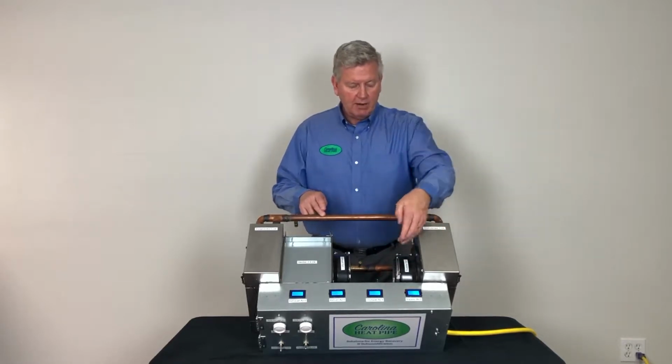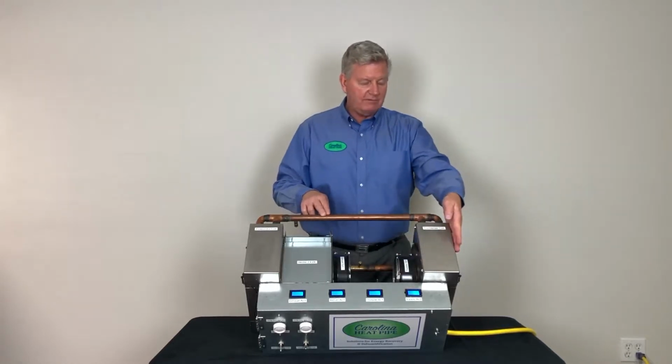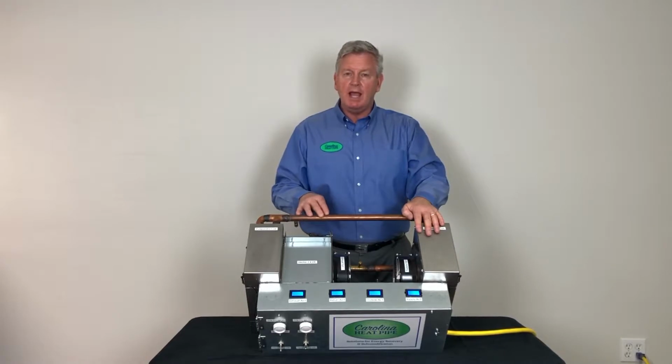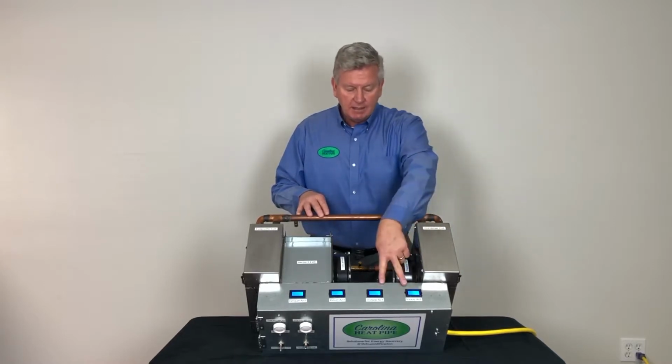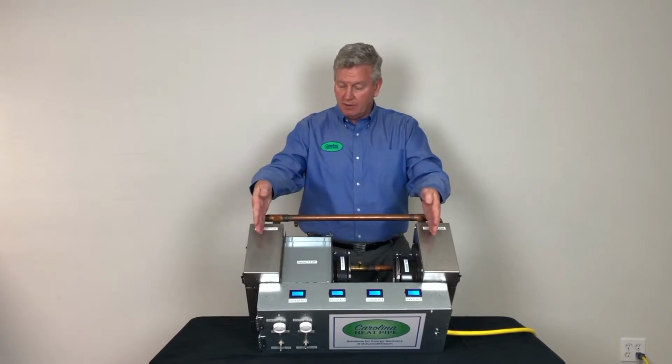The outside air is before the condenser coil. The supply air is after the condenser coil. The difference between the outside air and supply air is the amount of heat energy transferred by the condenser coil. In this case, about 15 degrees. The same energy transferred by the exhaust coil.